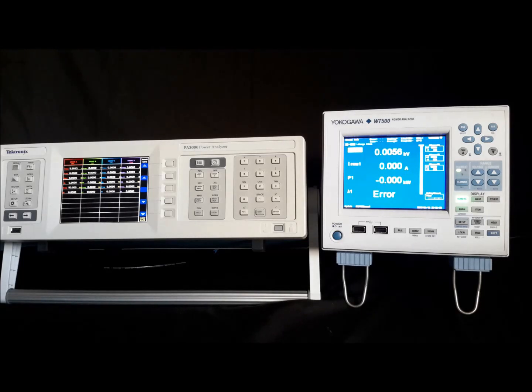Frequency bandwidths on the Tektronix are advertised to 1 MHz and the Yokogawa to 100 kHz. I know that Yokogawa do have higher bandwidth analyzers, but this is what I've got today. This is what I can compare one against the other with. Input voltages on both units, the Tektronix is at 600 volts RMS and the Yokogawa is at 1000 volts RMS. Input currents, 30 amps RMS on the Tektronix and 40 amps RMS on the Yokogawa.